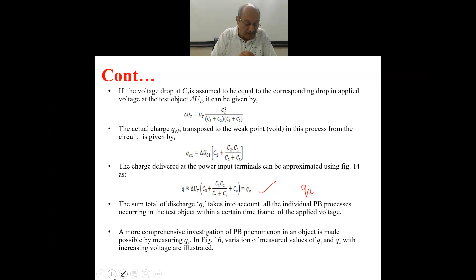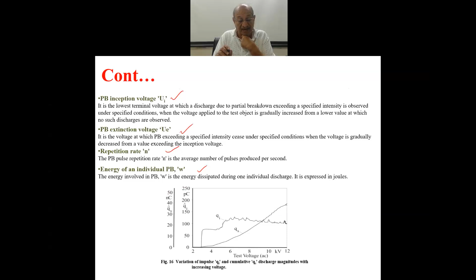So we have defined partial breakdown inception voltage, we have defined extinction voltage, the rate of repetition is given by N, how frequently it is repeated, and the energy in an individual partial breakdown, let's say, is W. When you measure the two types of partial breakdown, that is QI at the single location of maximum magnitude, and the sum total, with increasing voltage, the whole scenario may look like this. This is a measured result on an apparatus, and obviously when it is the sum total, the total charge will be more, so it is given here in nanocoulomb, and when it is measured for one single location of highest magnitude, it is in picocoulomb, as you can see.